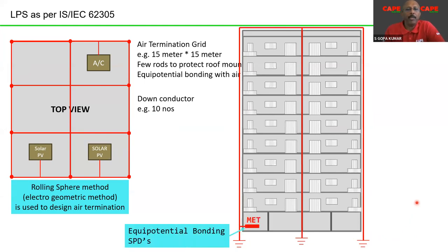The fourth subject, which is of equal importance, is equipotential bonding. What is equipotential bonding? You can see the down conductor is connected to MET. MET is nothing but the main earth bus bar of the mains incoming panel. The down conductor must be connected to the protective earthing of the electrical system, and equipotential bonding has to be made. When we talk about equipotential bonding, the down conductor and the earth bus bar can be directly connected. But this earth bus bar and the phase and neutral conductors have to be equipotentially bonded through a device called an SPD, surge protective device. So basically, your lightning protection consists of an air termination, a down conductor, an earth termination, and an equipotential bonding system consisting of SPDs.